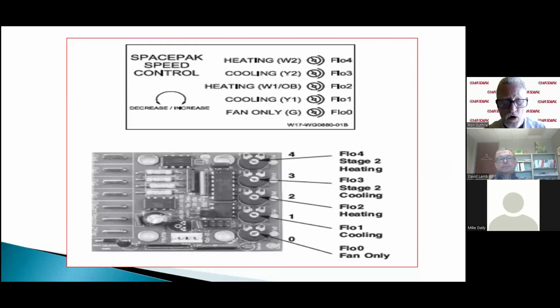All right, here's a picture of that EVO board. If you look all the way on the right-hand side of that board, there are tabs that you would use your meter on to measure the volts DC. There's a common one down at the bottom, and then you would measure each of those little rheostats for stage 2 heating, stage 2 cooling, etc. And you would measure the volts DC and adjust it with a control screwdriver to set the speed for that particular mode of operation.